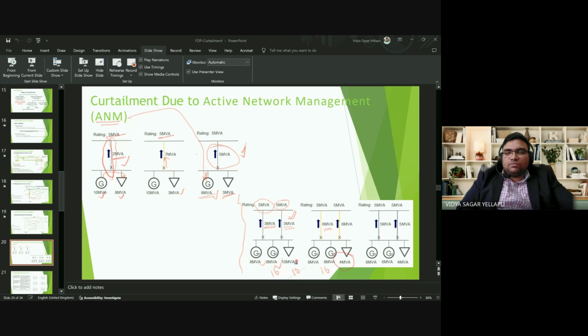The senior generators, which are ahead in the priority queue, are to be given more preference to produce more generation, that means generation as per their rating, and the junior generators are to be curtailed. That is the concept of LIFO, last in, first out. If you are connected to the network last, then you are the first to go out. In the case of any asset violation, if any asset gets overloaded, then the junior generator has to go out from the network. That is the concept of LIFO. So this generator has less preference than this generator.